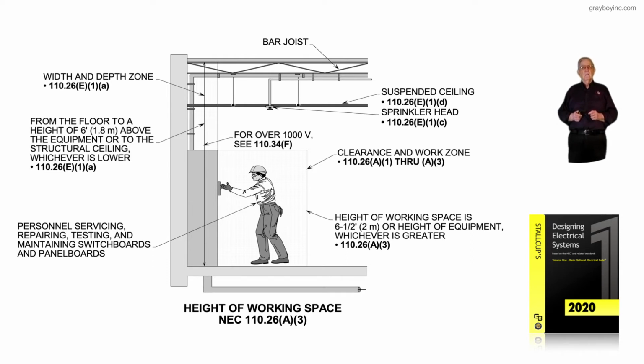Now, from the floor to a height above the equipment or to the structure ceiling, whichever is lower, we need that 6 foot and the clearance rules from the floor up. But now notice there's nothing below the panel. That switchgear, or switchboard, is sitting on the floor. And we have the personnel servicing, repairing, testing, maintaining a switchboard, panelboard, switchgear, whatever it might be.